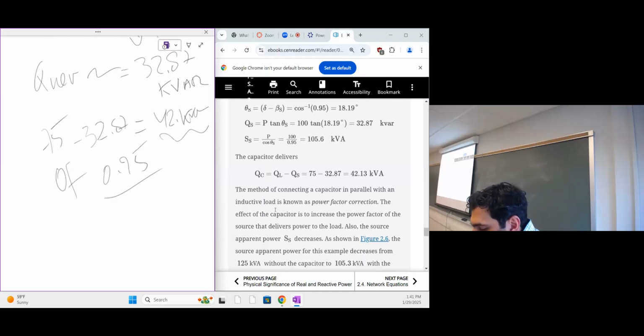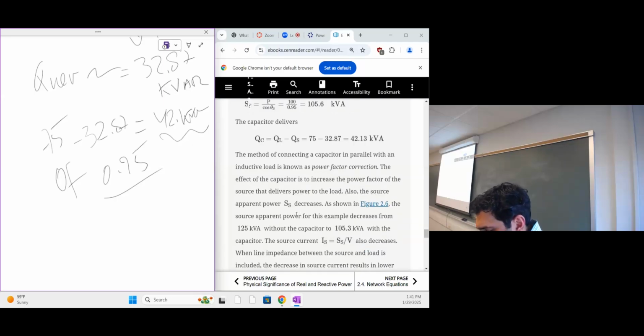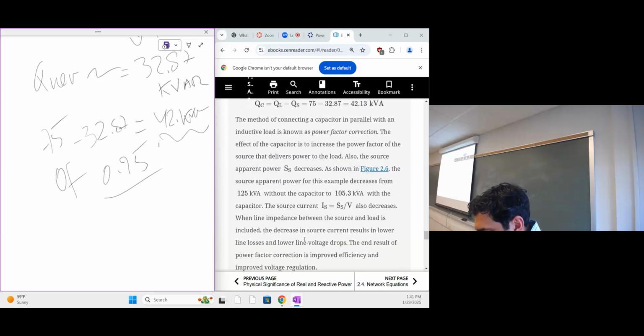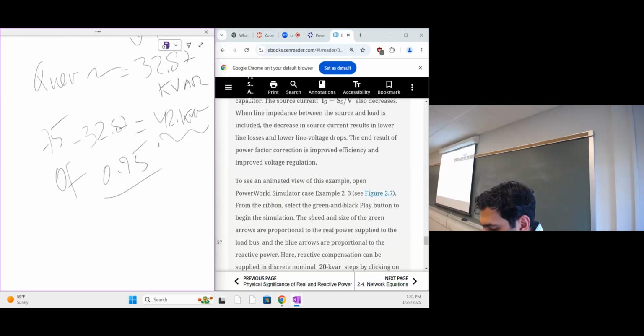So the method of connecting a capacitor in parallel with the inductive load is known as power factor correction. This is very important in power systems. The effect of a capacitor is to increase the power factor of the source that delivers power to the load. Also, the source apparent power S decreases. We've seen that. Now it's 105. It was 125. As shown from the figure, the apparent power decreases. Okay, I've said that. And it's really good to solve the issues of voltage drops. The end result of power factor correction is improved efficiency and improved voltage regulation.